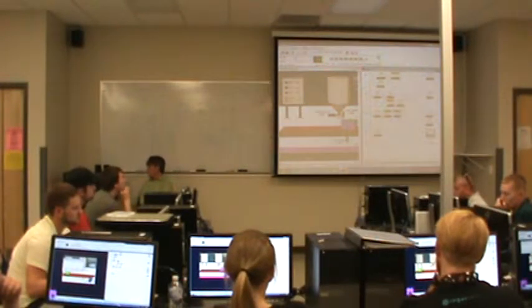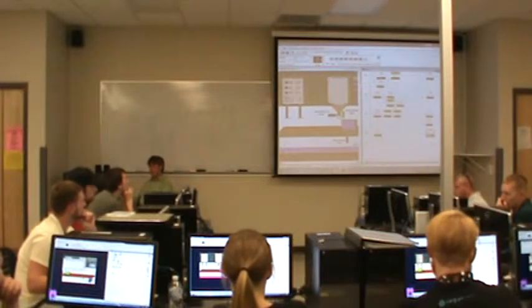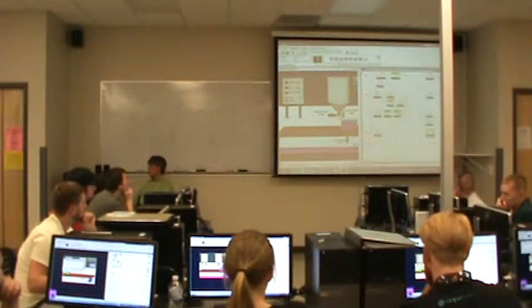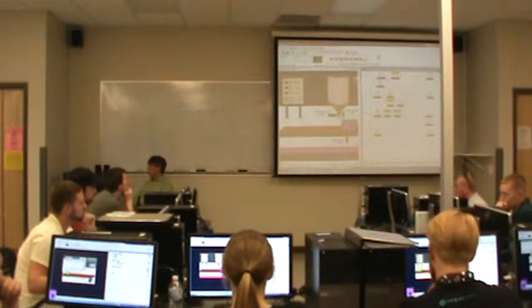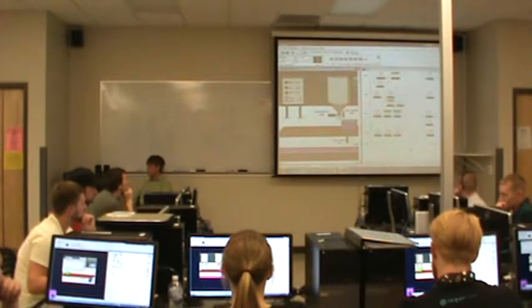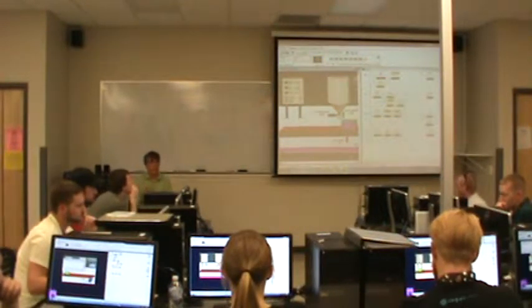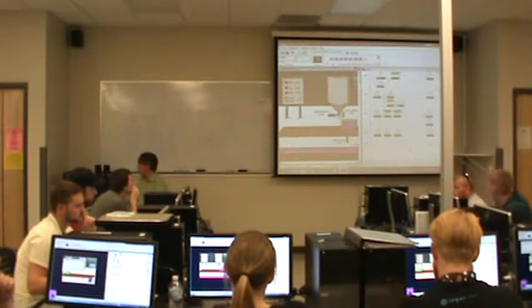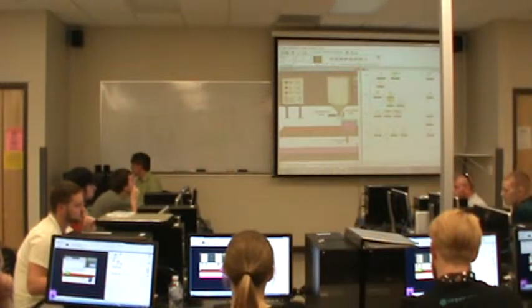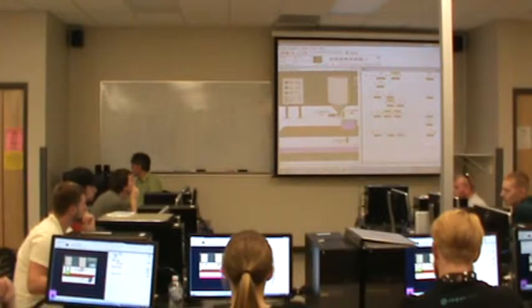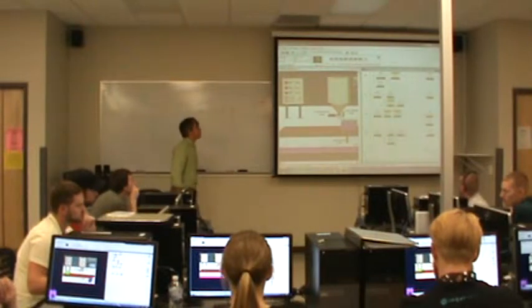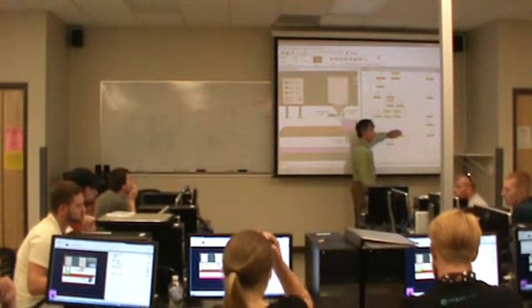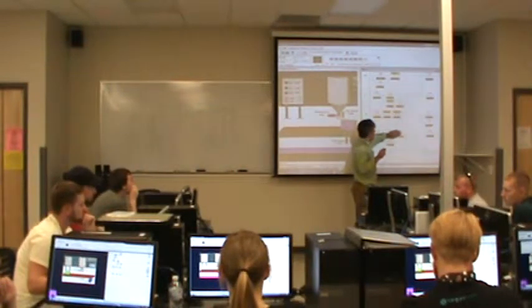So here's our full lamp, and basically what we want to do is have it seal itself in when a certain condition occurs. We want it to come on when both prox and level are true. Level's true and prox true. That is a very particular condition. It should come on when that condition happens, and it should stay on even when that condition is clear. Okay? So we have to OR around this and include a set of contacts so that it will stay on, right? So as soon as prox is true and level is true, we know the condition that has occurred, or the event that has occurred, is that we've got a full box.